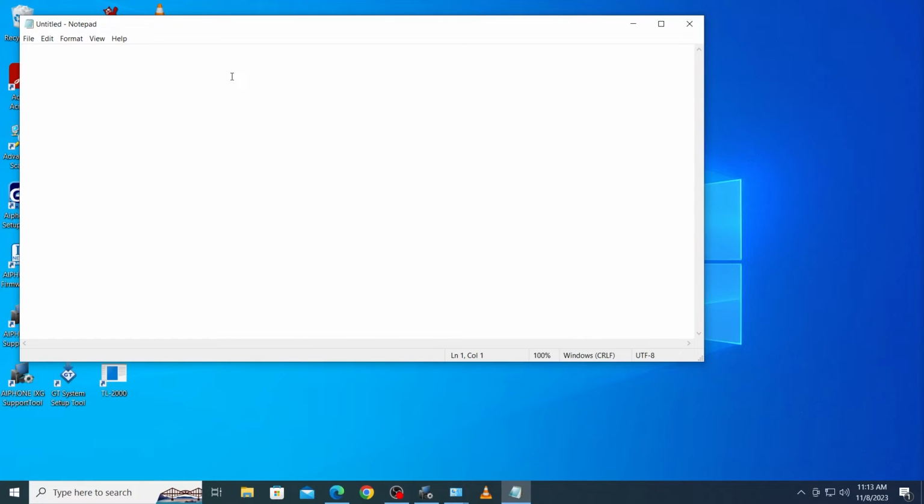More complex editors like Microsoft Word are not recommended, since they will often add additional information that will interfere with the programming. This is the case even if it is not visible in the final product. The format of the text file will be as follows: 0100, comma, the IP address of the IXW-MA, comma, 65014, comma, 1. Make sure there are no spaces between any of these sections.